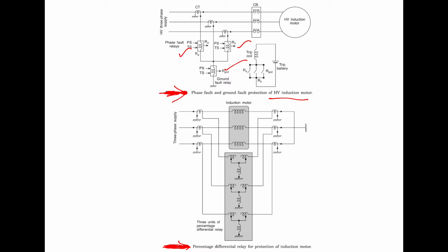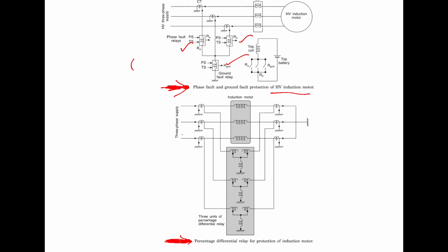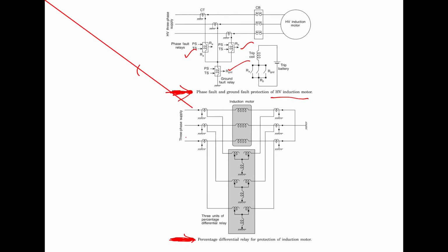This also we have discussed in the overcurrent type. It is similar to whatever we have used in the three-phase system or transmission system. So the thermal capability characteristics of the motor should be kept in mind while applying this overcurrent protection. The overcurrent relay characteristics should be below the thermal capability characteristic, as we have discussed. Now, in case of a high impedance ground fault inside the motor, so this is for phase and the ground faults.